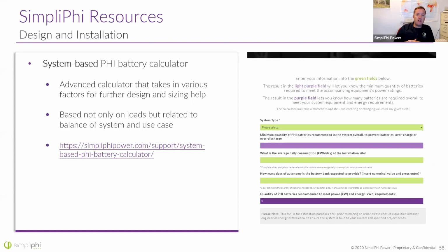This is going to help us make sure we don't exceed the maximum continuous charge and discharge rates of our batteries. Remember, we have a C/2 rating on our batteries, so you never want to charge or discharge faster than 1.9 kilowatts. This knows what pieces of equipment are capable of, and takes into account the days of autonomy and the consumption data we already entered, while also making sure equipment doesn't exceed that charge rate.